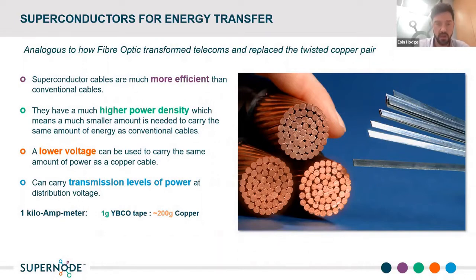Comparing directly to copper - it depends on application and design - but we like to propose a ratio in terms of current density of 1 to 200. In terms of cross-section, one of the tapes you see on screen per millimeter squared can be 200 times smaller than that of copper. That's obviously very advantageous in terms of the size of the cables and the challenges that exist around consenting when high capacity copper needs to be integrated into the system.